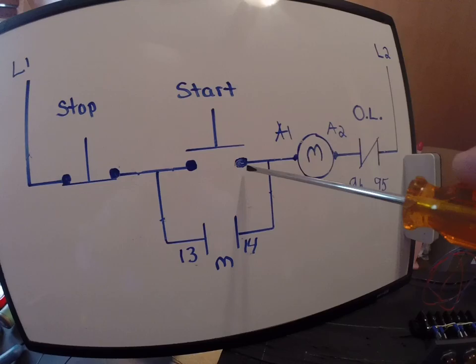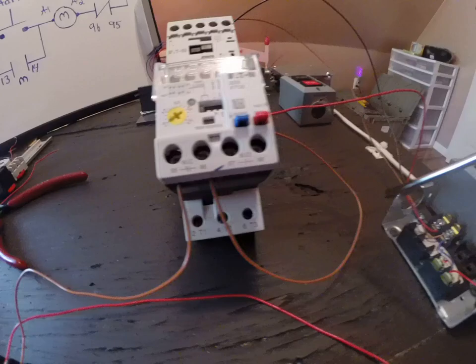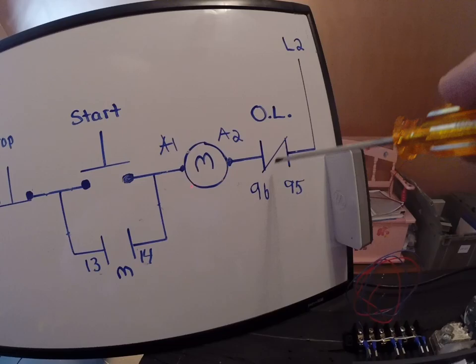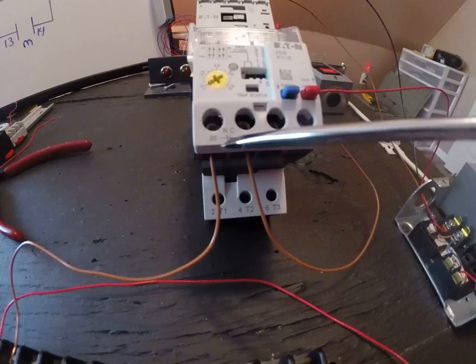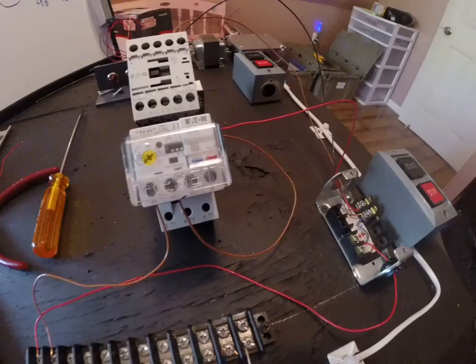Then I come off of A2 and I want overload protection, so I came off of A2 into my overload through a normally set of closed contacts back home to my source. And if it trips on overload that'll kill the circuit. So you'll see this running with indicator lights in the next video.